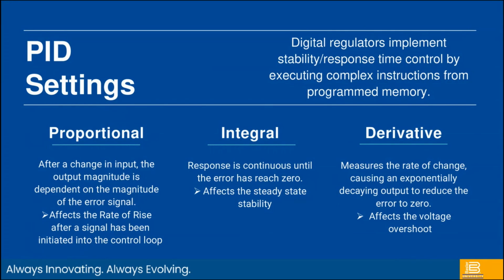So one of the things that always comes up when we talk about digital voltage regulators is I have to set the gains. I have PID settings. So here's a slide with a lot of words on it. I'll read the first part. Digital regulators implement stability response time control by executing complex instructions from program memory. So a lot of words that basically are saying now I have a microprocessor. So rather than using circuitry to do my stability response, I'm going to use numbers and gain settings, and my microprocessor is going to calculate, based upon what I tell it, how much output to give to make corrections to the voltage. And it does that by using three sets of gains. We use proportional gain, integral gain, and derivative gain.